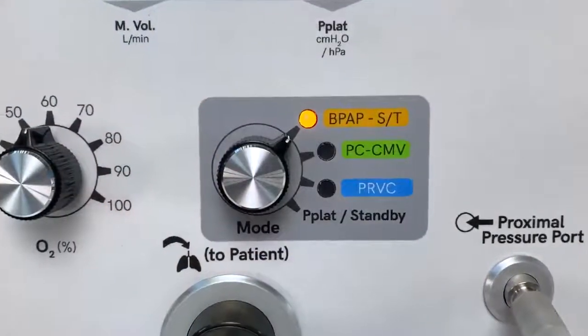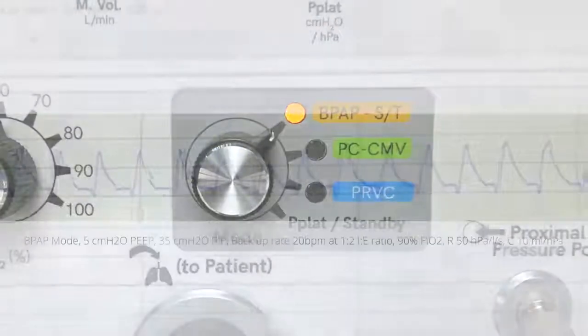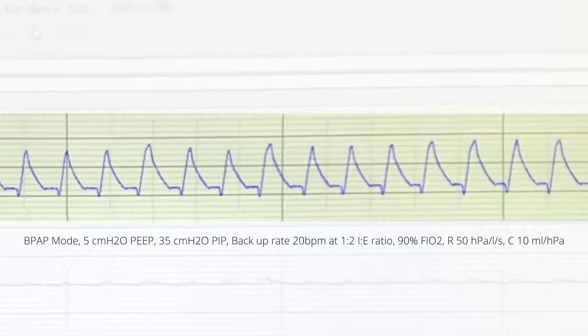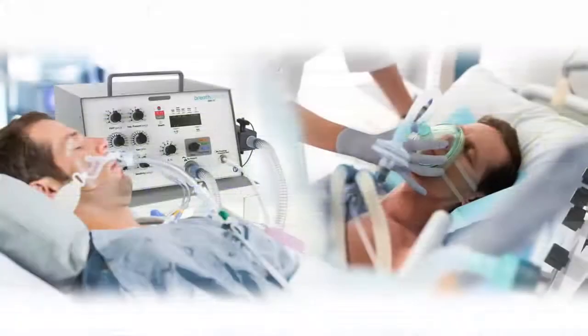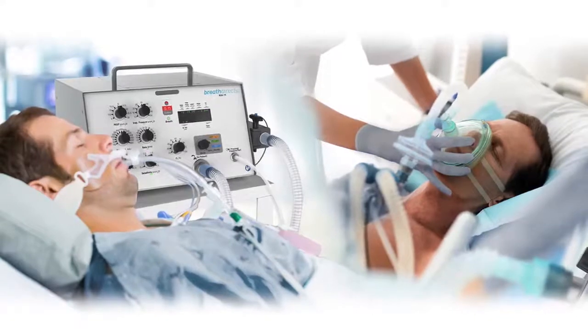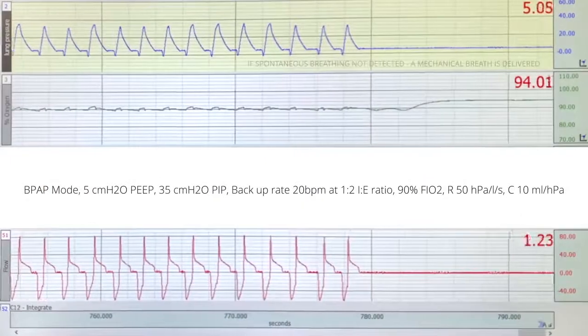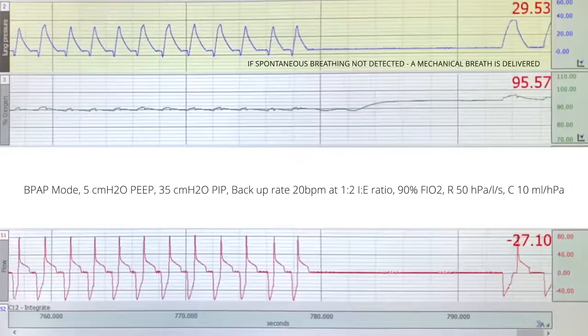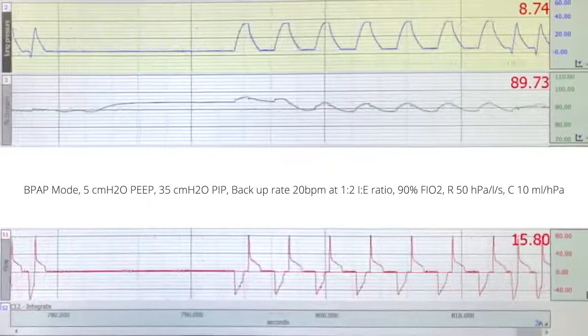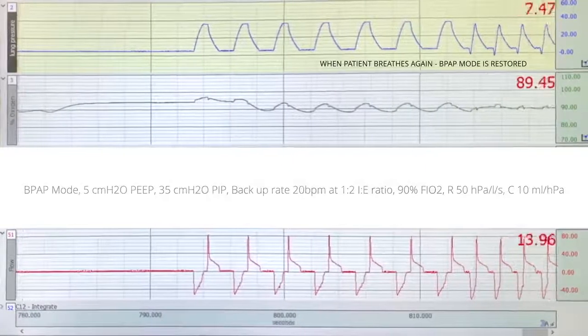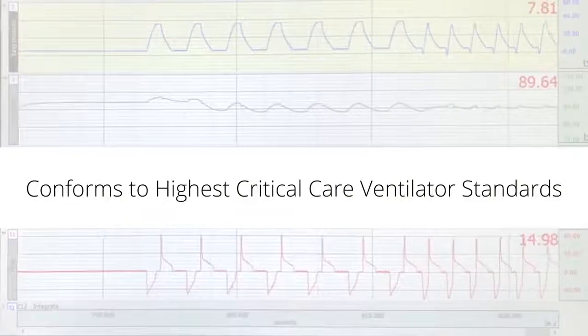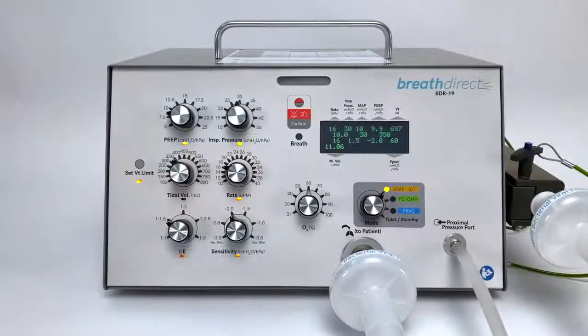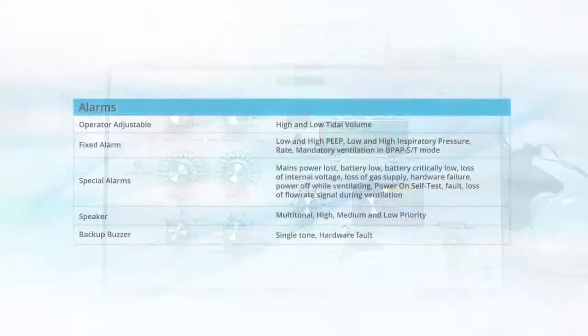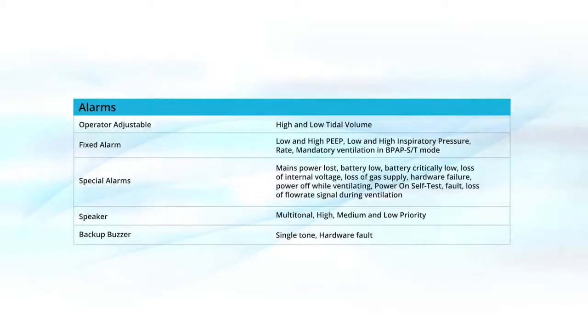In BPAP, a continuous flow is delivered to the patient at the set PEEP level. When the patient draws a spontaneous breath, the pressure level is raised to the inspiratory pressure support level. This mode can be used as supportive ventilation with an intubated patient or a patient with a non-invasive mask. If the ventilator does not detect a patient's spontaneous breathing, a mechanical breath will be delivered based on the set backup rate, PEEP, PIP, and FiO2. If the patient then begins to breathe again, the BPAP mode is restored. This important backup function conforms to the highest critical care ventilator standards. The BDR-19 has a full complement of alarms, including user-adjustable tidal volume alarms, and will automatically set PEEP, inspiratory pressure, and rate alarms. It also includes an apnea alarm when in BPAP mode.